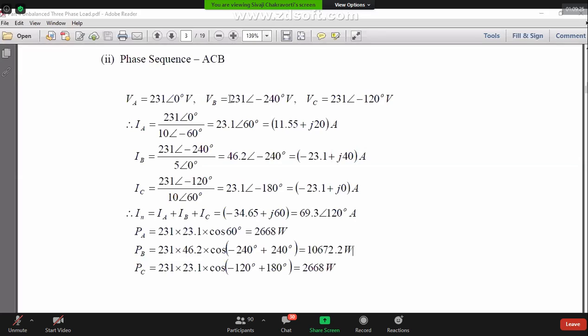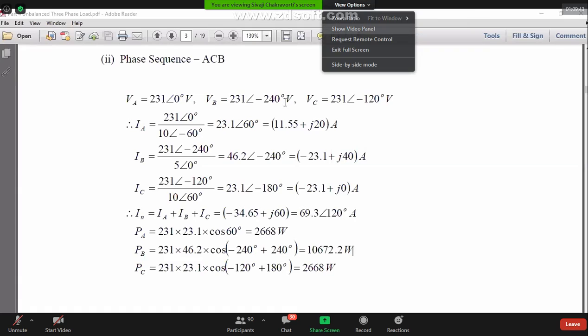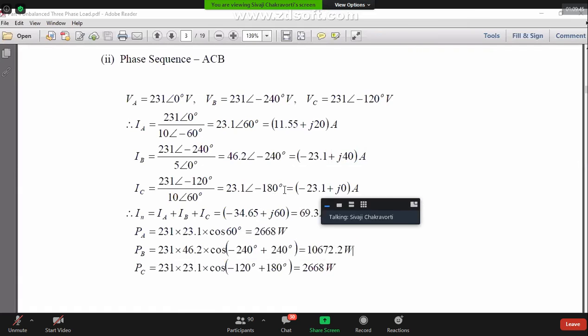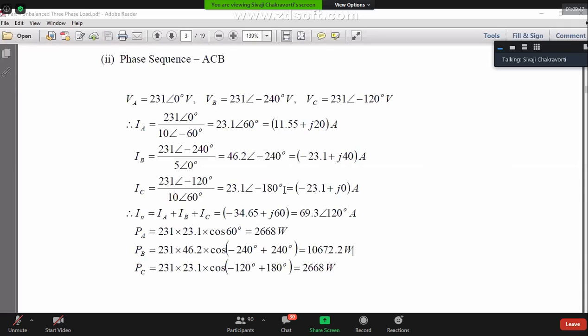And if we make a mistake in properly connecting the three phases, then you have this big problem: where normally you are expecting almost zero current in the neutral, there you can expect as high as 3 times the phase current, and that could be a disaster. I mean, if it is a practical power system, it will be a major problem.